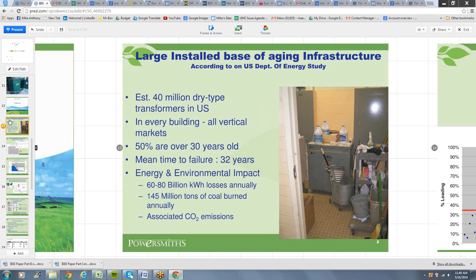In terms of these transformers inside the building, these low voltage dry type transformers, we're talking about 40 million of them around the country. They're in every building, doesn't matter what vertical market, whether you're a hospital or a school. According to the DOE, over 50% of these transformers are 30 years old or more. When you overlap that with the mean time to failure of a low voltage dry type transformer at 32 years, you can see there's going to be quite a bubble of activity, should we say, related to transformer replacement over the years.